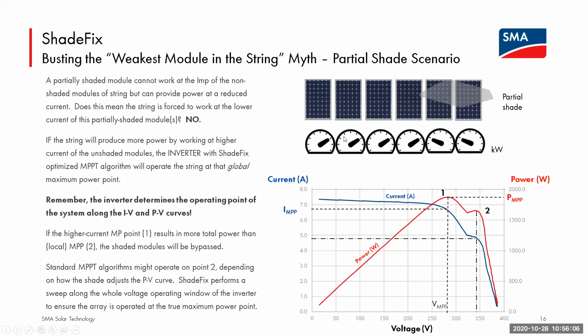And so here we see full speed or power from modules 1 through 4, but then modules 5 and 6, instead of being fully blocked by a hard shaded object, this partial shade or diffuse irradiance causes those modules to not drop to 0, but drop to a lower power potential. And we see that translated down on our IV curve in the form of not a loss of complete voltage, but we get humps in our IV and power curves. And what's happening here? So as the irradiance lowered on these 2 modules, their potential contribution is basically lowered.